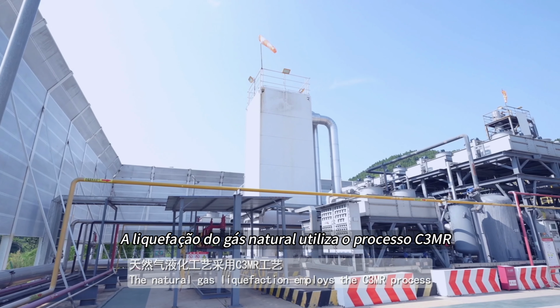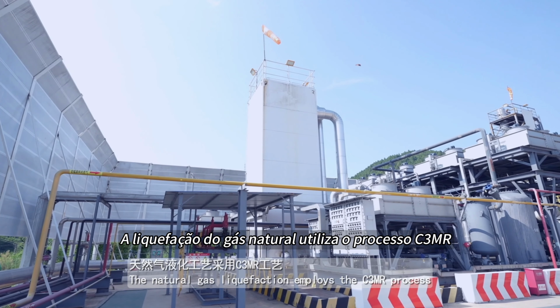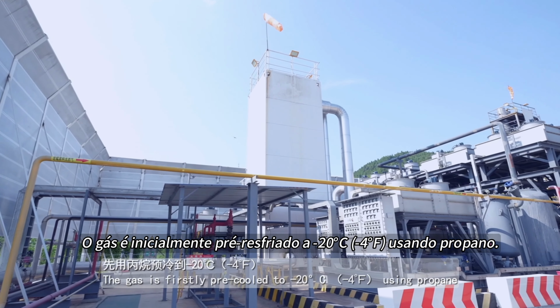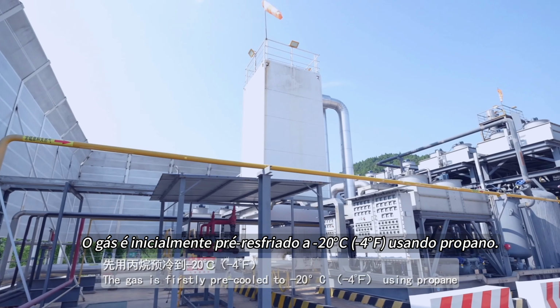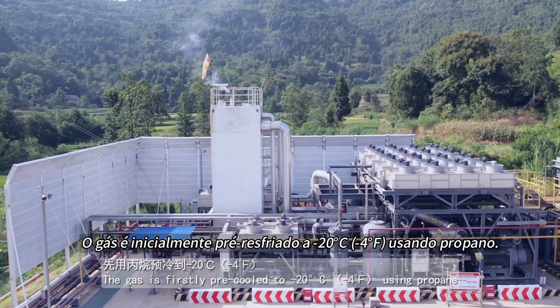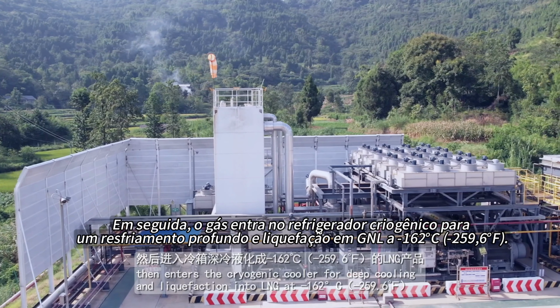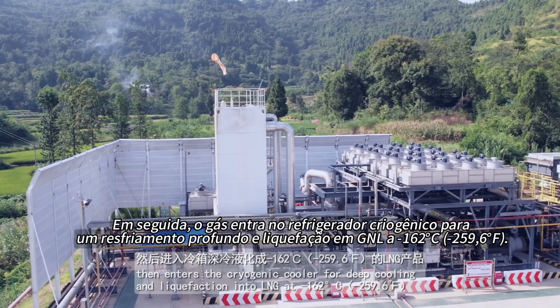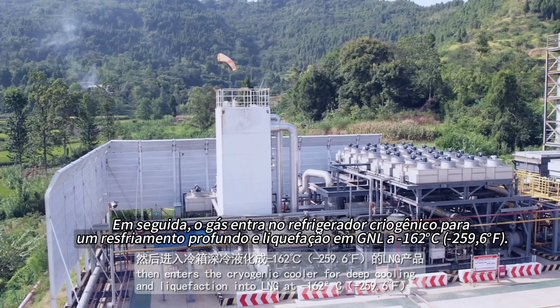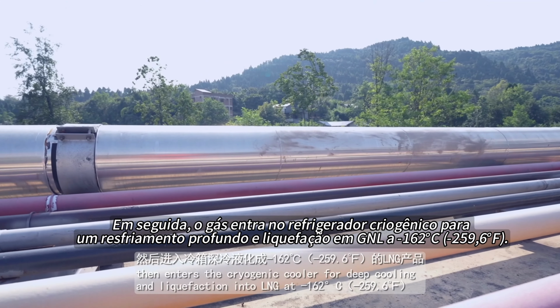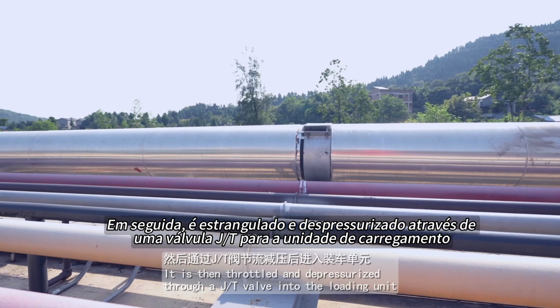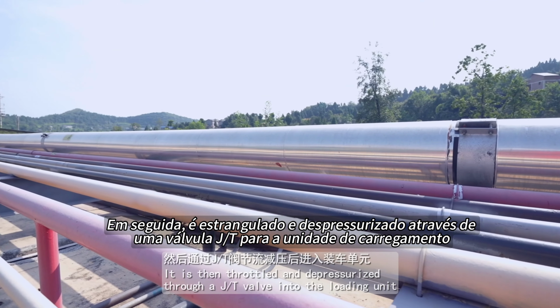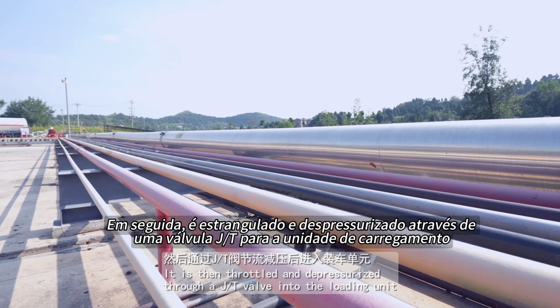The natural gas liquefaction employs the C3MR process. The gas is firstly pre-cooled to -20 degrees Celsius using propane, then enters the cryogenic cooler for deep cooling and liquefaction into LNG at -162 degrees Celsius. It is then throttled and depressurized through a J/T valve into the loading unit.